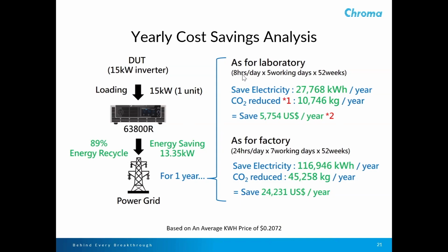In this test, we had a 15 kilowatt inverter as the DUT, and we're using our 63800R regenerative load to test it. Over a 1-year period, based on an average kilowatt hour price of 20 cents, the average price in California for 2022, with a regenerative energy cycle rate of 89%, you'd save approximately $5,000 a year for a single lab. If you're using this in a factory or production environment around the clock, you can see upwards of about $24,000 worth of savings per year.